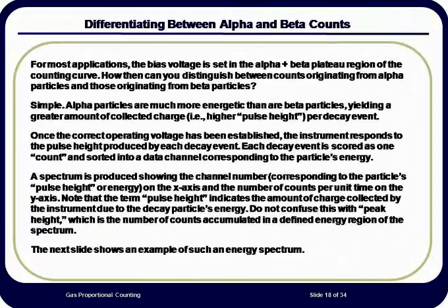We had noted earlier that the pulse size, that is, the height, generated by an alpha particle event is much larger than that generated by a beta particle event. Each event is a single count, and the height of the pulse obtained from each count is measured. We can distinguish between alpha and beta particles based on this height. First, the pulse is collected, and then it is assigned as an alpha or a beta count based on its height. The term sometimes still used for a spectrum of accumulated counts versus energy is pulse height analysis, or PHA.